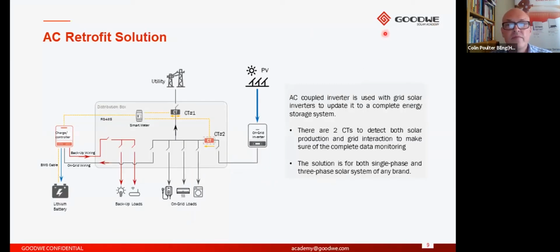All right, so that's a bit about the operational logic of our hybrid inverter. So we ought to take a look here at our AC coupled, or our retrofit solution. So what you can see here is a scenario where perhaps this is a customer that got their original inverter installed within the property, and now we've added in on the left hand side here all the equipment which is necessary to perform the battery storage. So here you can see our charge controller. In exactly the same way that our hybrid inverter would work in terms of charging and discharging, so will the charge controller work in the same way. But of course, you don't have any direct PV input into the charge controller.